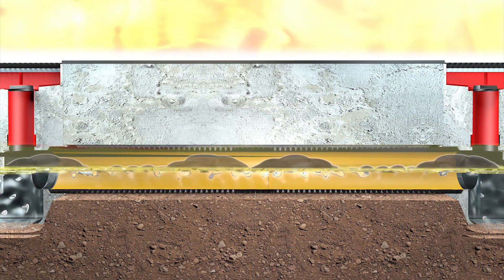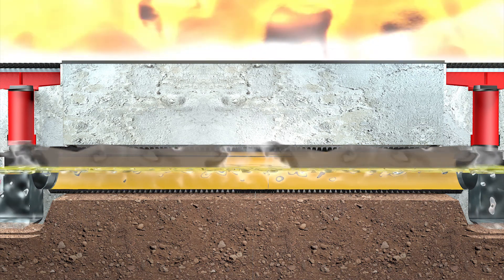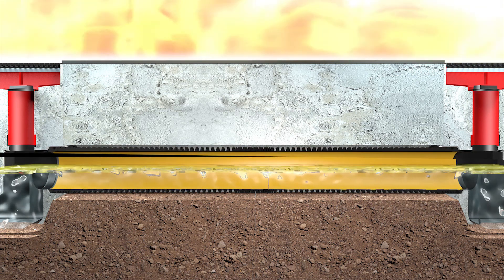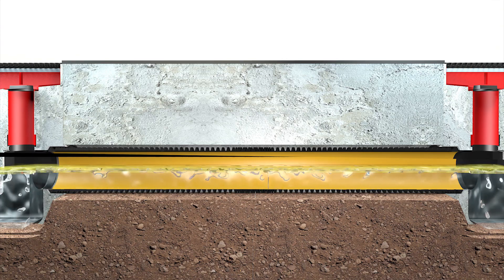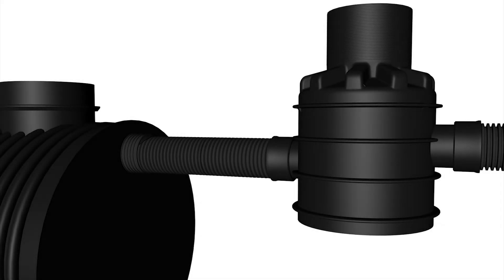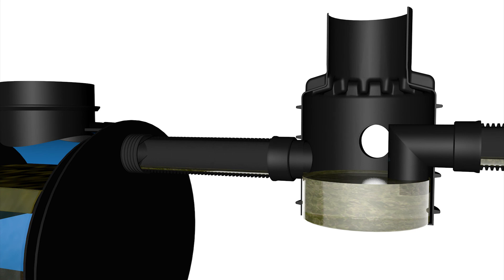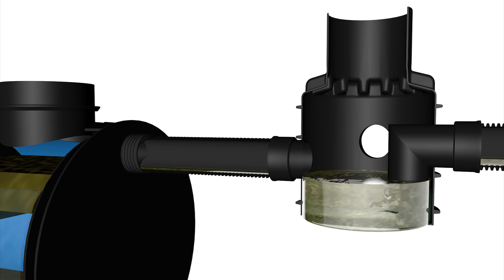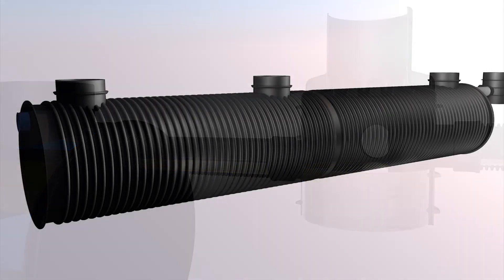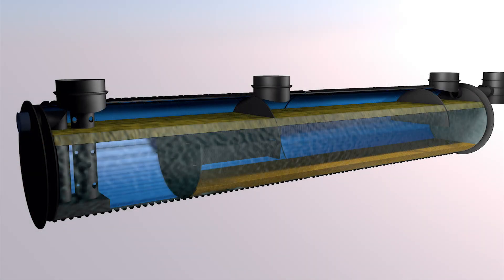The double siphon no-fire gully guarantees the presence of water inside the bottom tank in order to prevent air entrance inside the system. Flames might spread inside the system, but they will extinguish immediately because of the lack of oxygen between two gullies. In the meantime, the tunnel firefighting system will dilute the flammable liquids inside the drainage system using water flows. In case of light liquids spill, they will be channeled from the drainage system to the safety bypass manhole, where they will mix with water and end up in the last tank.